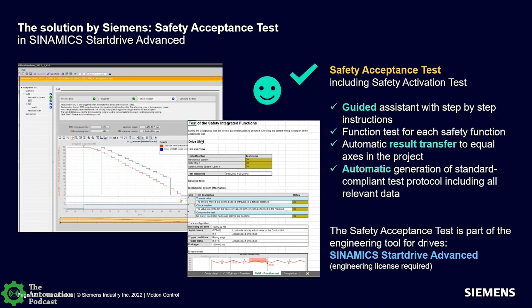This says the test functions that were set up. This is the verification that they were run. So if we see here in this one example, it might be an STO, and I'm going to verify that when somebody hit that safe stop 1 from max speed, the machine stopped in 3 seconds. And so in case anything ever changes or there is an accident, you go back and you have the verification here, okay, here's the verification that this machine would stop from max speed in 3 seconds with the safe stop 1. So that's a big part of it, and making sure that you have your documentation on your machine as well with these safety functions.